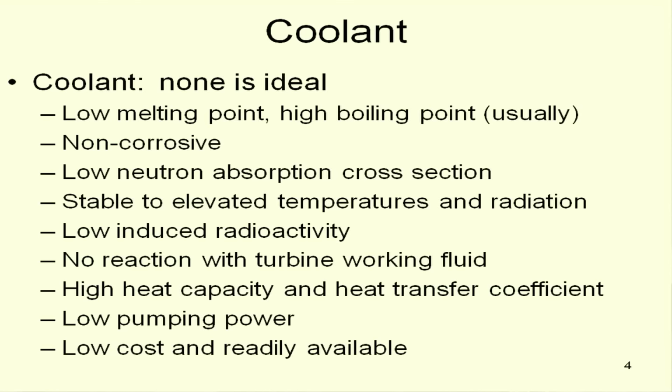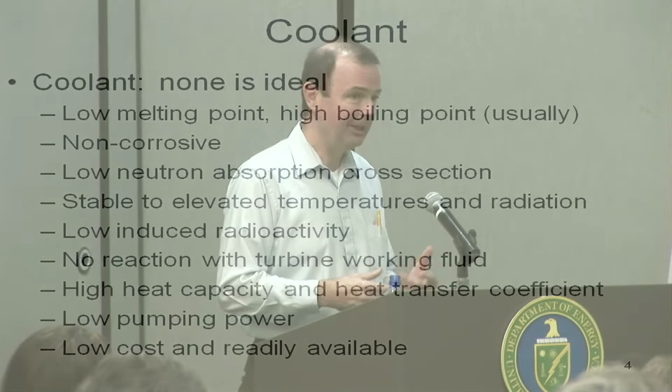The kind of things you want is you want a low melting point. In other words, you don't want to have to worry about keeping your reactor warm to keep the coolant from freezing up on you and then have to reheat it. And usually you'd like a relatively high boiling point. And that's, as pointed out this morning, if the boiling point isn't high enough, then as you go to heat it up, the pressure increases, which means the higher pressure, everything's got to be thicker, more massive, and more risky to some extent. Now, there are cases, if you're in a reactor where you want your coolant to boil, well, that's a little bit different. But for the most part, I think a high boiling point is good.